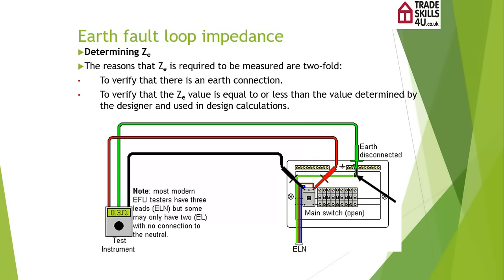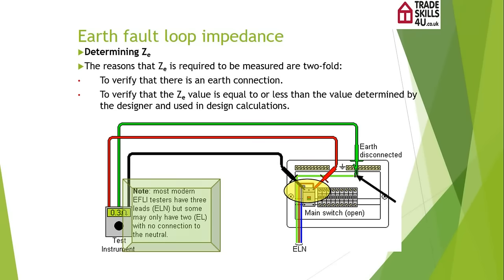Once we've isolated, we can disconnect the conductor, clamp onto it, and then our other two leads on our meter go around the incoming line and the neutral tails, which obviously will still be alive. Most modern earth fault loop impedance testers have got three leads, so they need the neutral in order to conduct the test. However, some newer meters have only got two leads, so it will be a question of reading your manufacturer's instructions as to whether you need two leads or three.